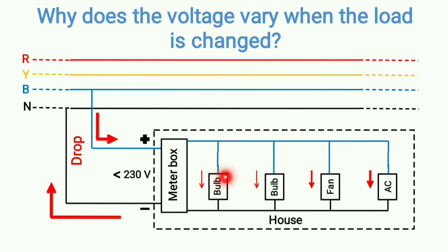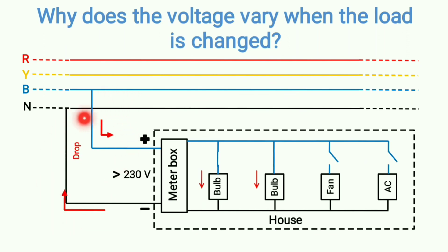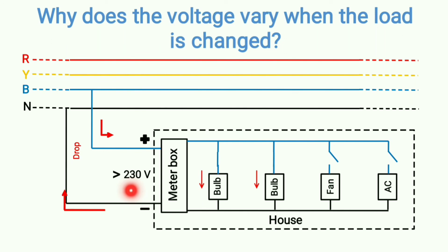Now suppose the power consumption is reduced — two loads are disconnected. The drop is reduced because now only the two bulbs are drawing current and they don't draw as high a value of current. As a result, the current in the service main also reduces, the voltage drop reduces, and accordingly the voltage at the consumer end will be higher. Again, if this voltage change is within plus or minus six percent, it is okay; if it exceeds the limit, you need to perform voltage control.